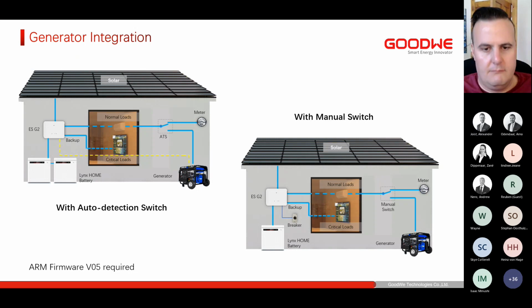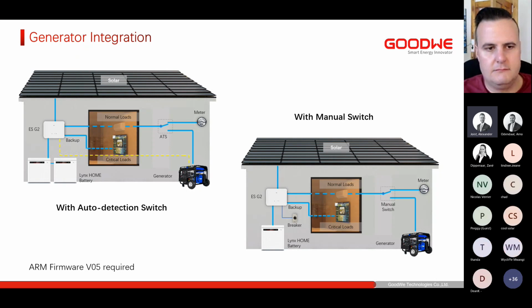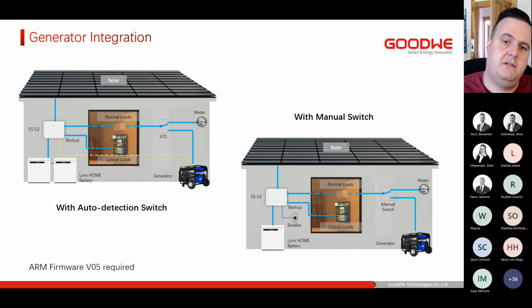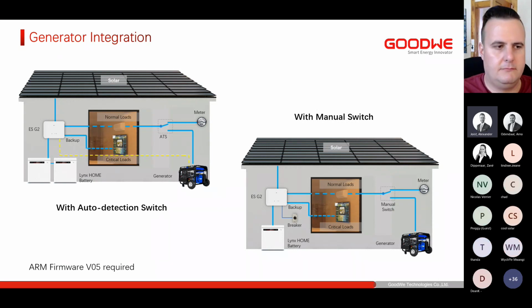Yeah. But even if the whole system shut down and there is no generator, on the next day when the PV comes, the inverter would actually start up again, right? And charge the batteries and would work again. Yeah, the inverter will start up, charge the batteries first to a certain percentage. Once it has reached a certain percentage, it will then start the backup output. Okay, perfect. So then the off-grid capability is actually fully there. Yes. Okay, perfect. Yeah, thank you.